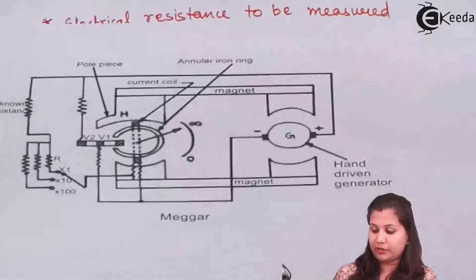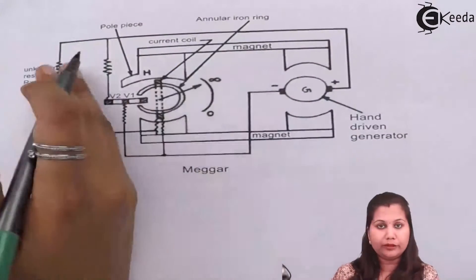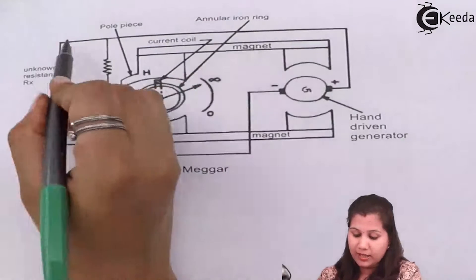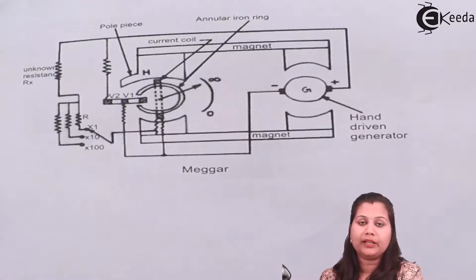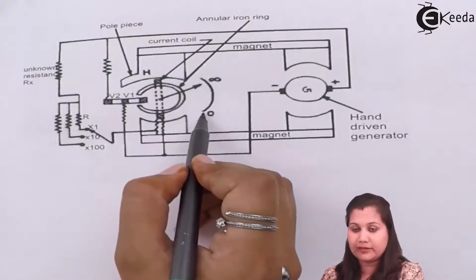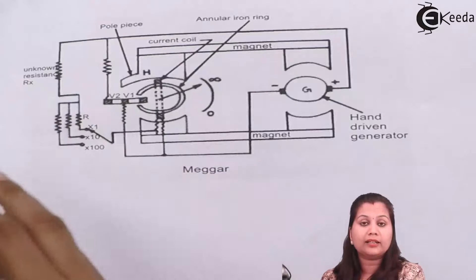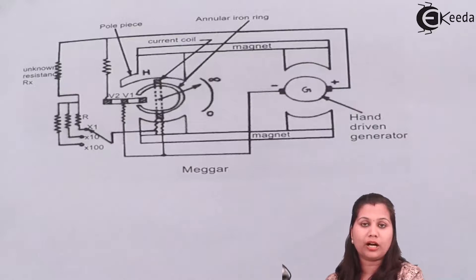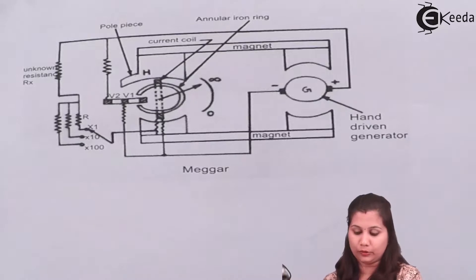If the unknown resistance is of very high value then no current will flow and the pointer will be at the infinity position, meaning the current coil is in a very weak magnetic field. When the unknown resistance is at an intermediate value — not very high and not very small — the pointer will be between zero and infinity. When the unknown resistance is negligible the pointer will be at the zero position and a large amount of current will be flowing in the circuit. This is how the Megger is used for measurement of unknown resistance of the order of 100 kilo ohms or 0.1 mega ohm and greater.